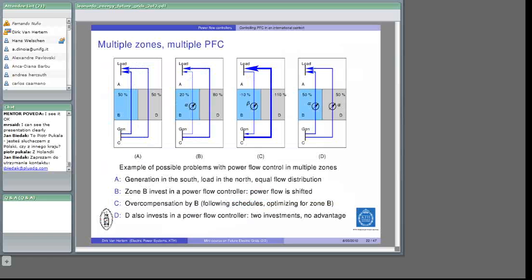In case zone B decides to build a power flow controlling device, he can shift the power, let's say, from 50-50 to 20-80 instead. And in the third picture, you can even assume that he goes to minus 10%. This seems unreasonable, but maybe this minus 10% was decided the day before in capacity planning, the settings were set, and some event made it completely different. Of course, you can see this is not optimal for the system at all. In the last picture, picture D, it's even worse, because zone D also invests in a power flow controlling device, and he cancels the operation. So 2 companies or 2 TSOs have invested in an expensive device which is not very useful.